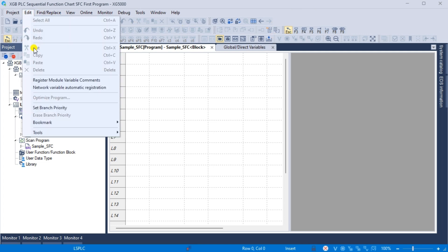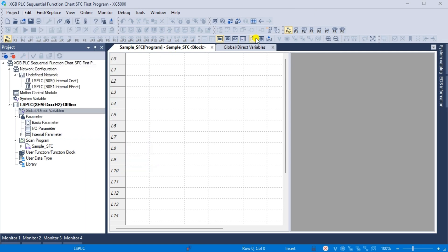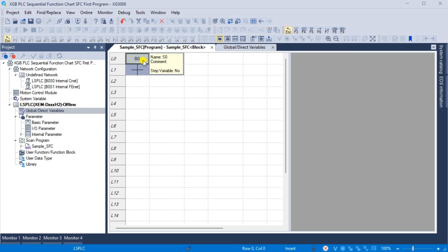Create the SFC program for the XGB PLC. Select the sample SFC program window. You can now create the sequential function chart code. All available commands for the SFC are under the main menu, Edit Tools. The shortcut function keys are also listed to the right of each command. There are also SFC command icons on the main menu in the XG5000 programming software. Click the step command F3 and move your mouse to the sample SFC program area. Click the spot where you'd like to place the step and transition. The step is set to the default of S0; double click to change the label. We will leave this as the default S0.